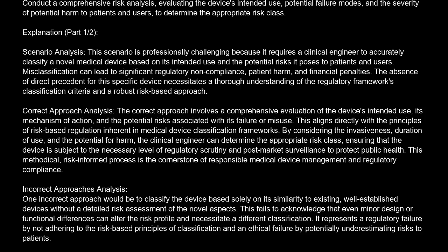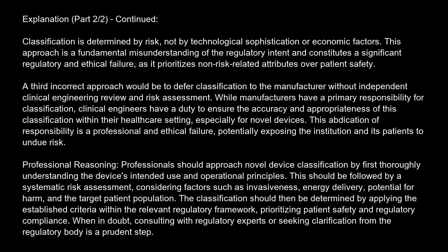Another incorrect approach would be to classify the device based on its perceived complexity or the cost of its components. Classification is determined by risk, not by technological sophistication or economic factors. This approach is a fundamental misunderstanding of the regulatory intent and constitutes a significant regulatory and ethical failure, as it prioritizes non-risk-related attributes over patient safety.